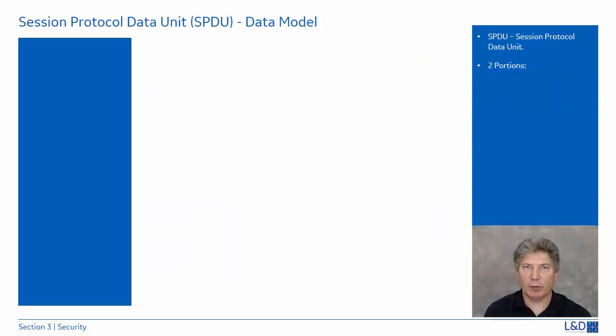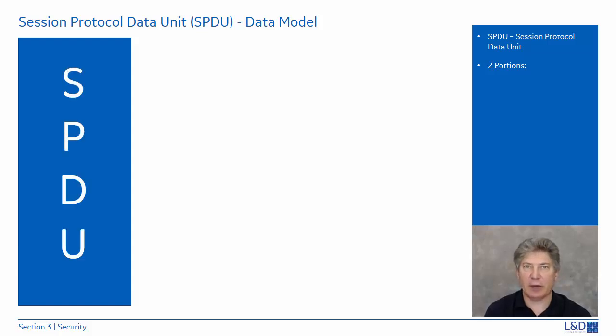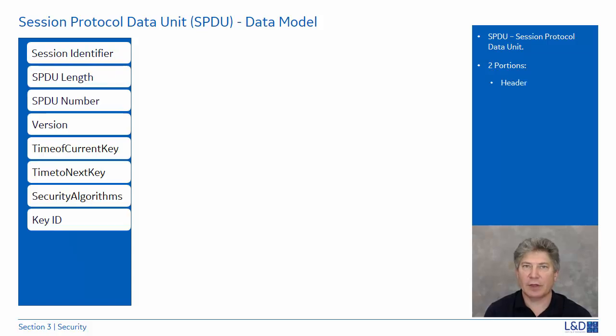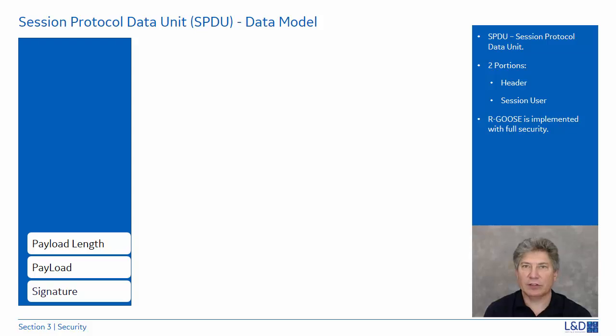With all the security defined, the routable GOOSE is encapsulated in a very unique data packet. IEC 61850-90-5 provides the capability to convey messages in a data packet known as the Session Protocol Data Unit, or SPDU. This supports the secure tunneling of the internet-based GOOSE to facilitate easier exchange between substations and control centers. It has two portions: a header and a session user. Let's quickly review each part of the SPDU.